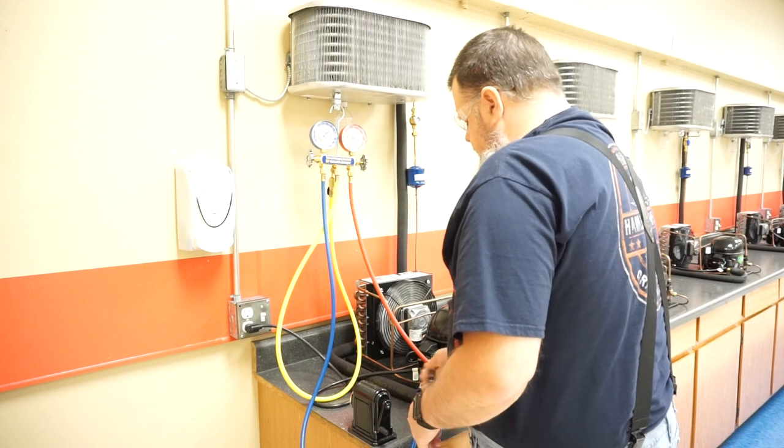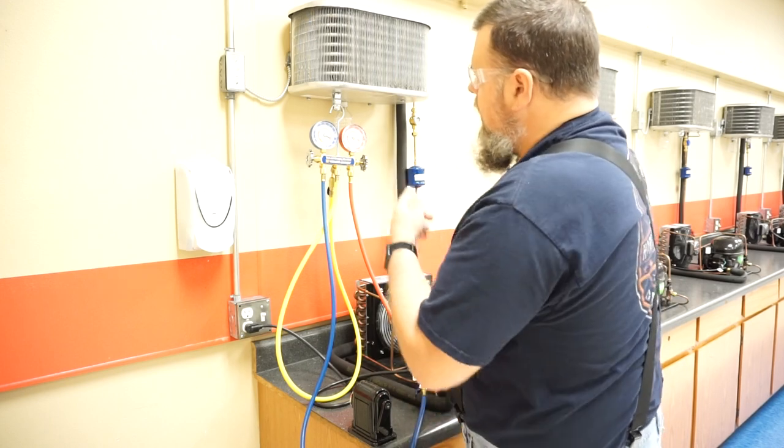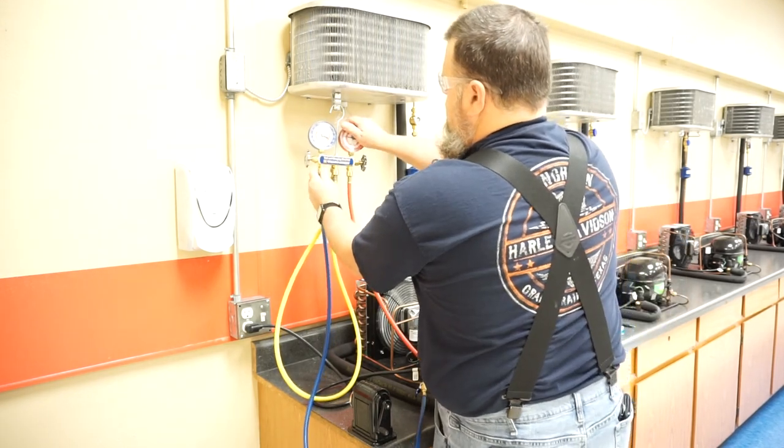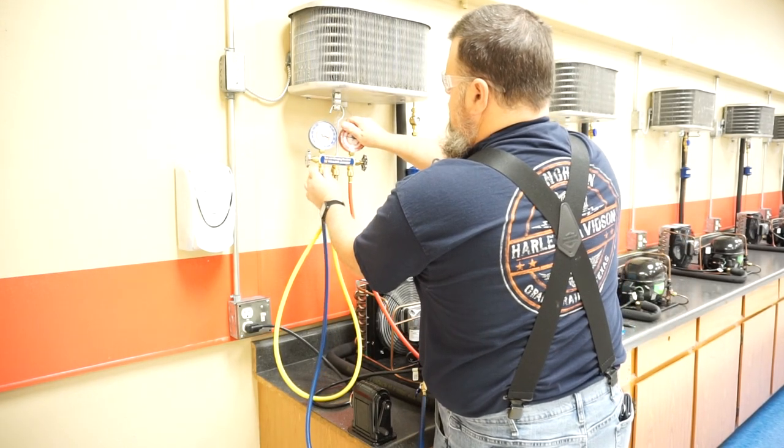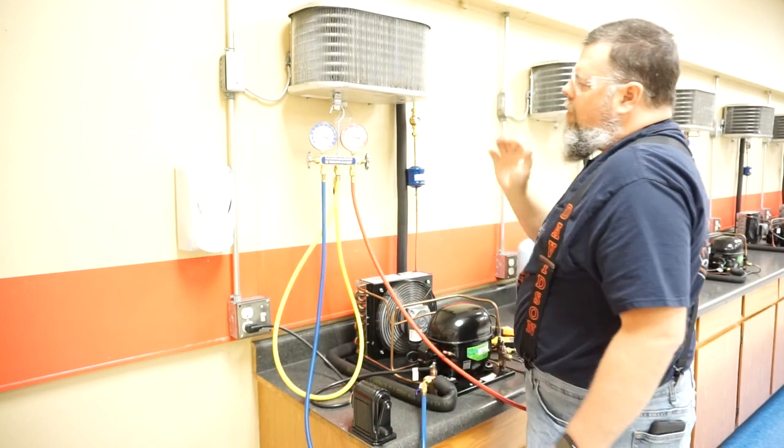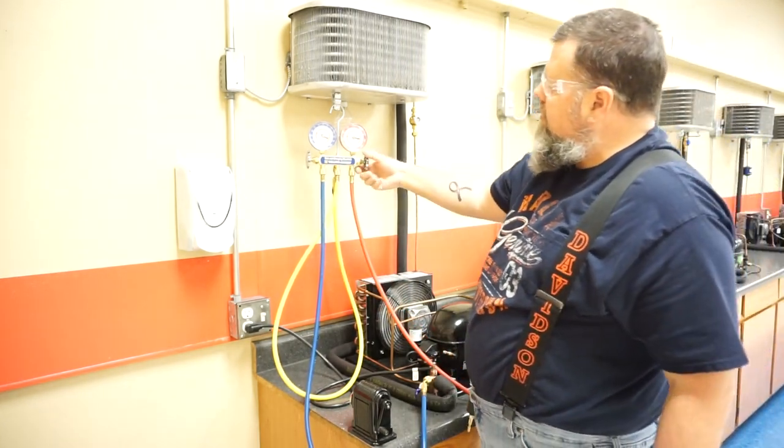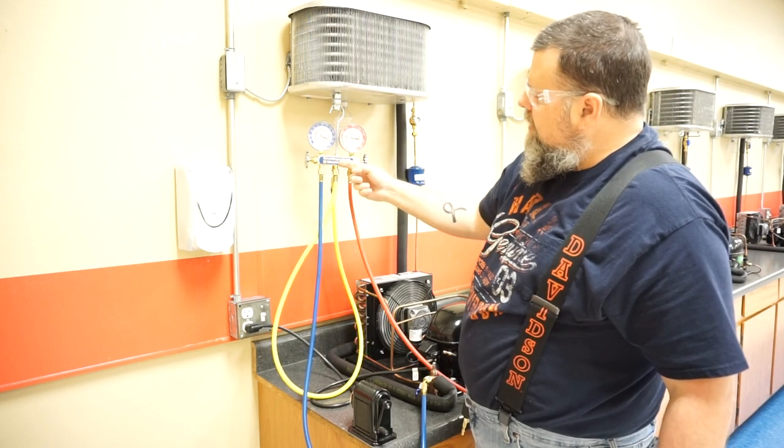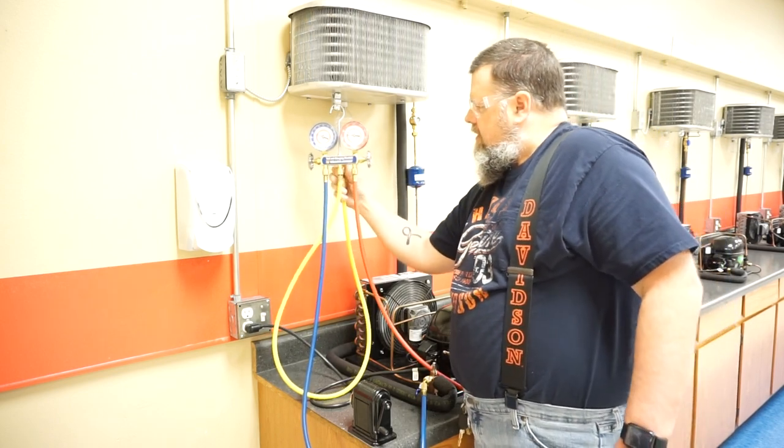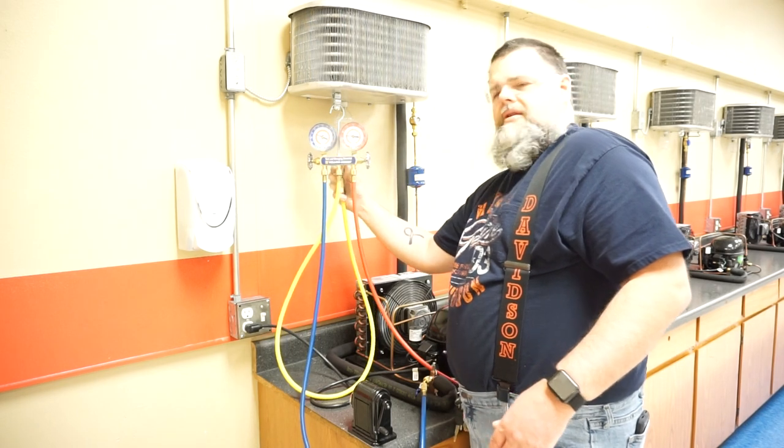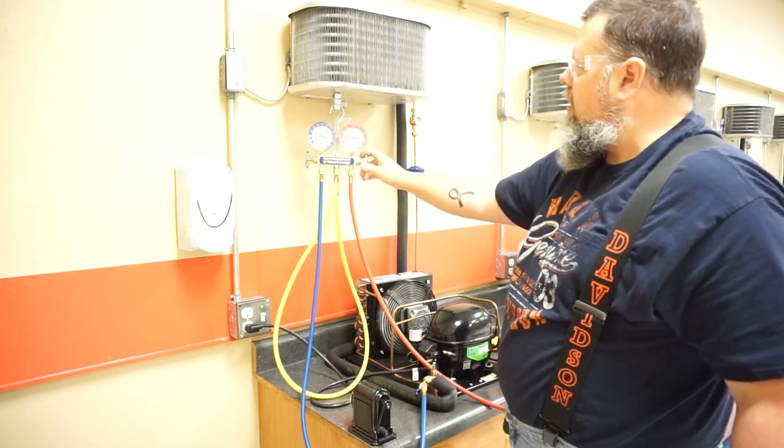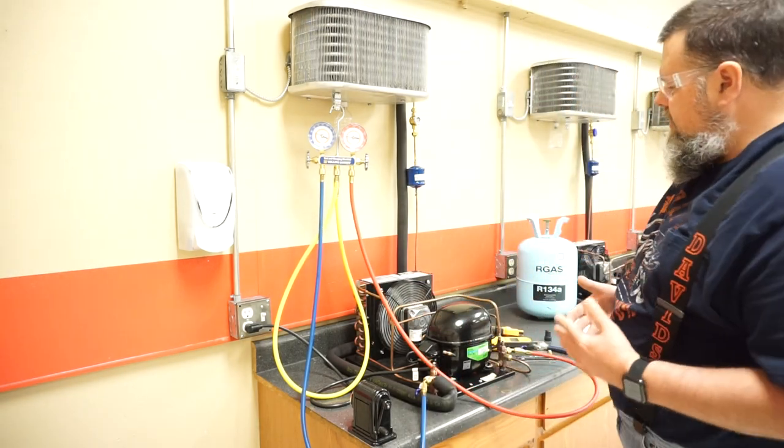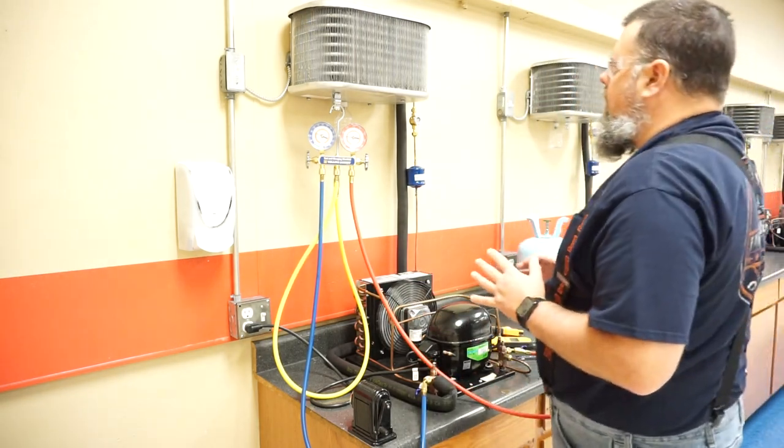I'm going to open this one up. Now I can see my low side pressure. I'm going to go ahead and purge this. Now I want to purge this yellow line. So I'm going to open this up for a split second, get a little bit of refrigerant inside here. That's all I need, just a quick, that is called a de minimis amount. We want to make sure we have no air in the system.